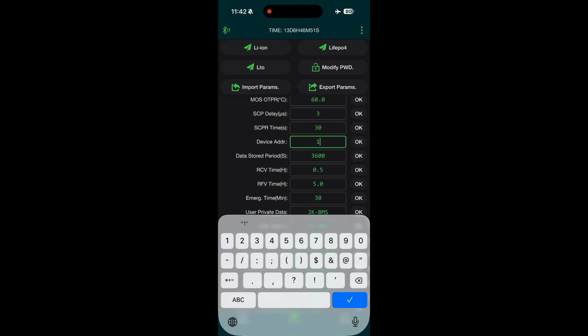Okay, data store period. This is how long you want the BMS to actually store data. Now it's in seconds, so 3,600 seconds is 1 hour, and if you activate that setting in controls, this is how long it will actually store the data for. Okay, so RCV stands for requested charge voltage, and this is basically how long the BMS will hold at the absorption charge. Now I changed that from 0.5, or if you want to leave it at 0.5, that's fine. I change it down to 0.1.